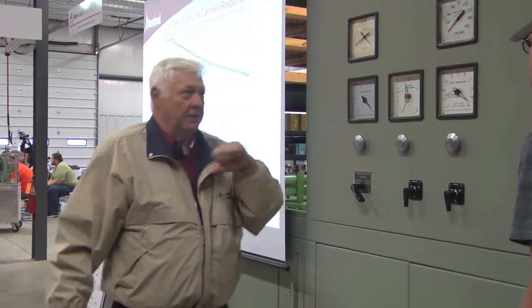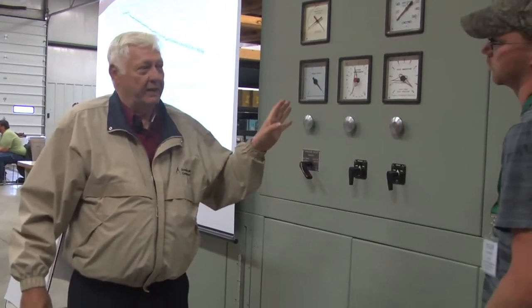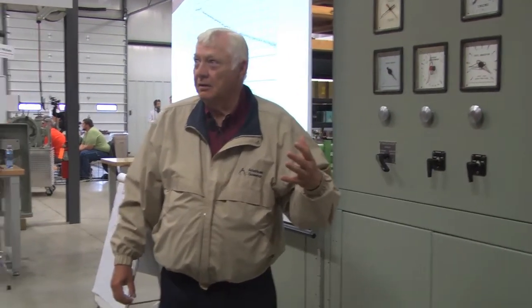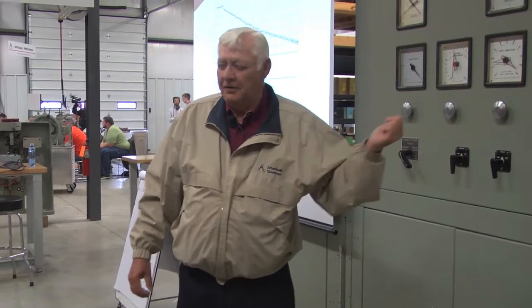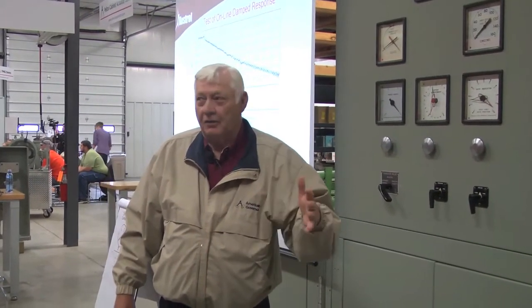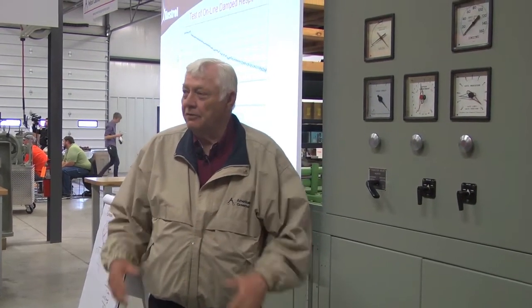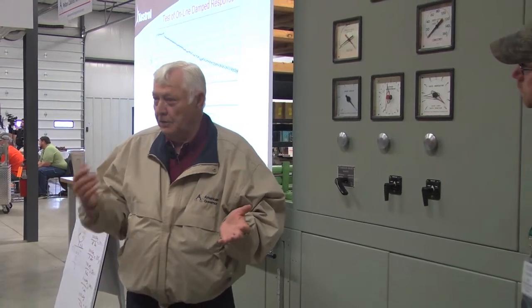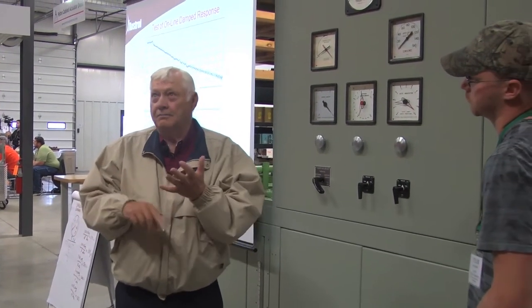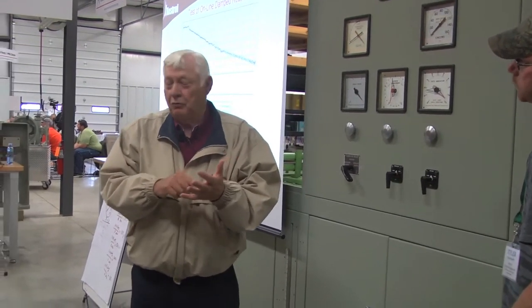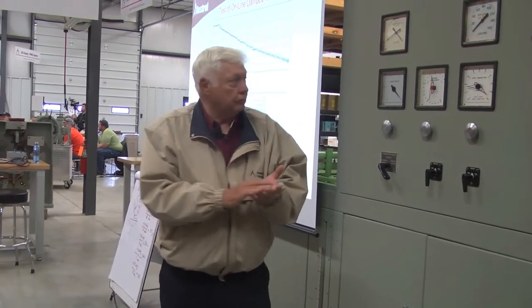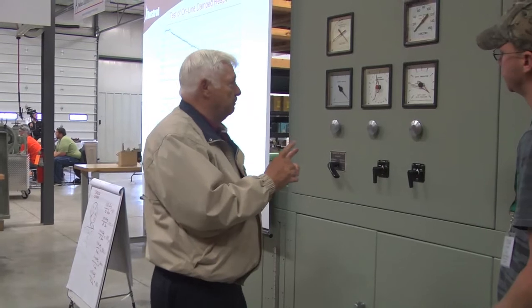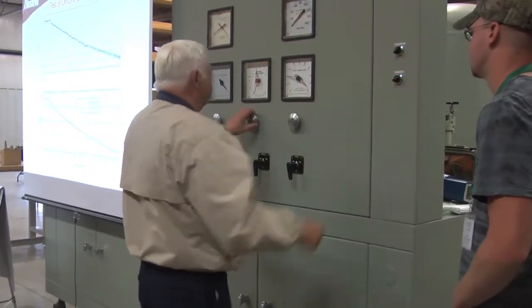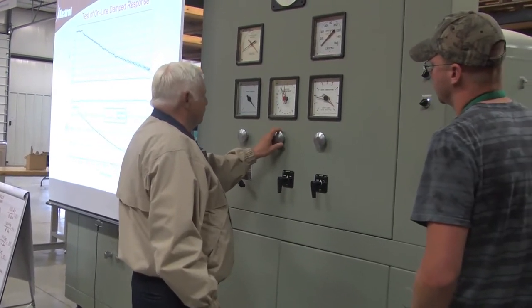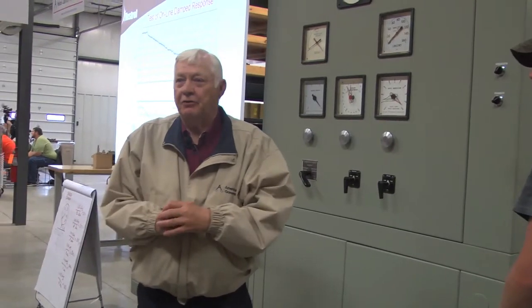Now, because I've done the work for you, if I put that dash pot at a half a turn, it's got 7-second timing. And if I put it at a quarter of a turn, it's 10 seconds. A quarter is 10, half is 7. So now you've got everything you need to know about this unit: the proportional gain, the KP, which you'd call temporary droop, and the dash pot reset time. Now, the other thing we can do is get this unit back at 98% and open the dash pot to a half a turn, please.